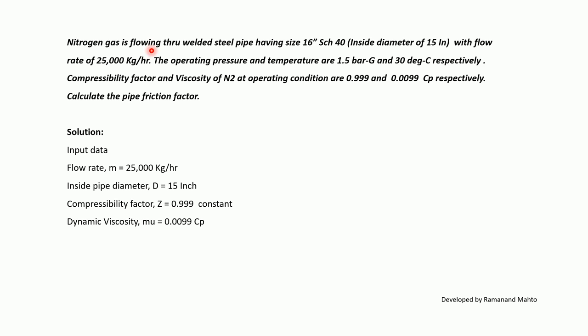Example problem: Nitrogen gas is flowing through a welded steel pipe of size 16" with 15-inch inside diameter, at a flow rate of 25,000 kg per hour. Operating pressure and temperature are 1.5 bar gauge and 30°C respectively. Compressibility factor Z = 0.999 and viscosity of N₂ = 0.0099 cP. Calculate the pipe friction factor.